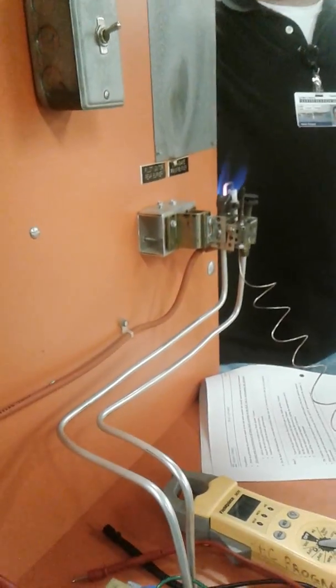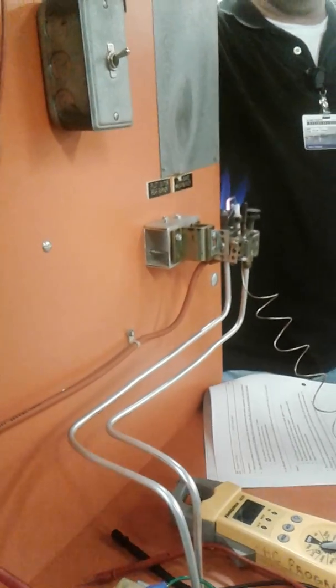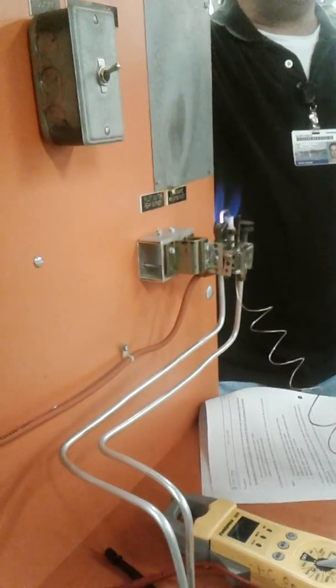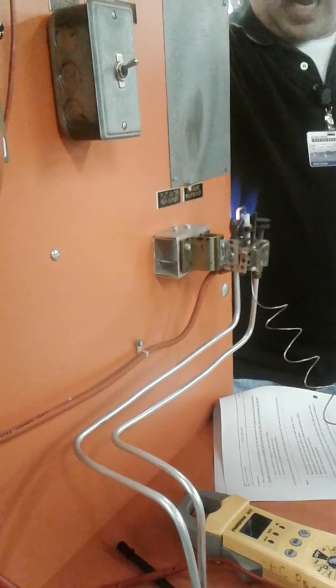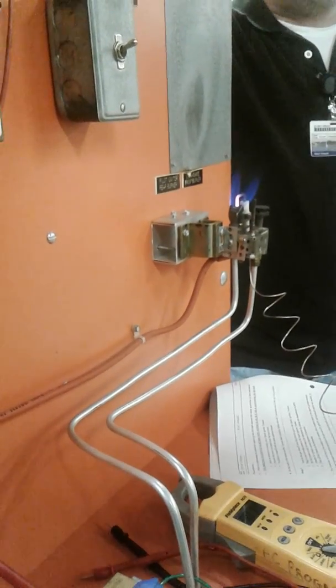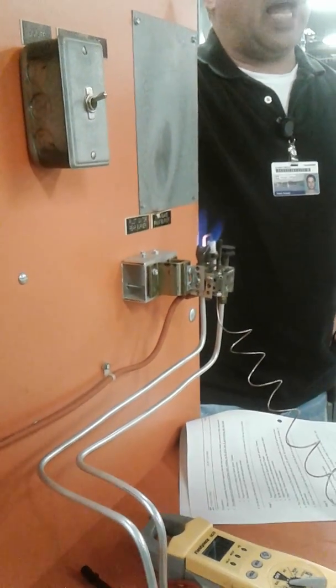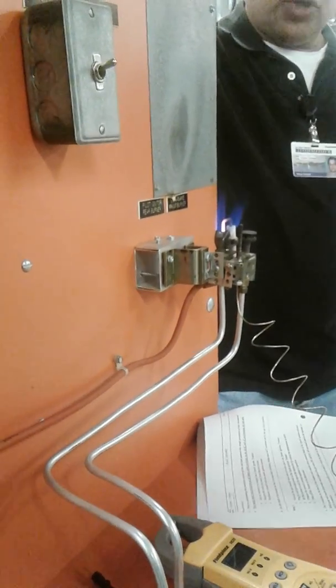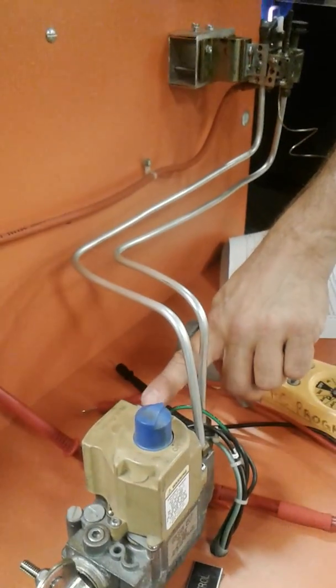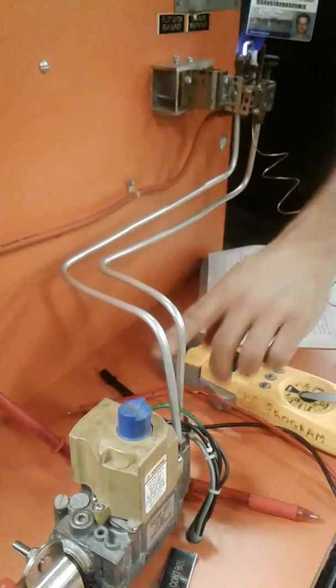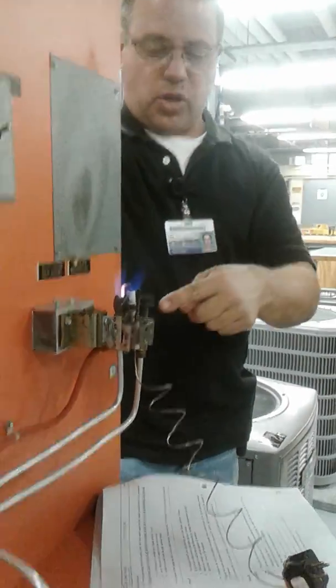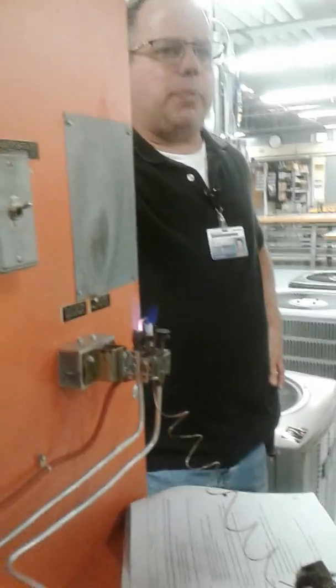So I'm going to tell you what's wrong, okay? I'm just going to tell you from experience. We're not allowing 24 volts to the gas valve. Or if we are allowing 24 volts to the gas valve, it should be open, right? So if we read 24 volts at our gas valve at the main valve, MV and MVPV, because MV and MVPV should have 24 volts to call for our burner. If we have 24 volts to this, it's not opening. What's wrong? The gas valve is bad. We're giving it the power, but it's not opening.